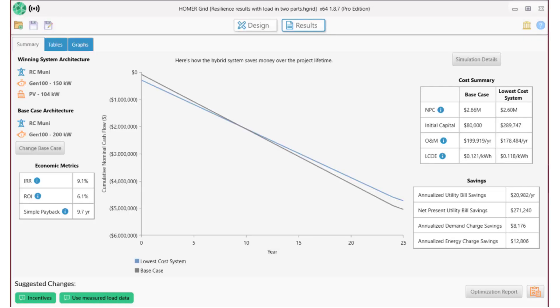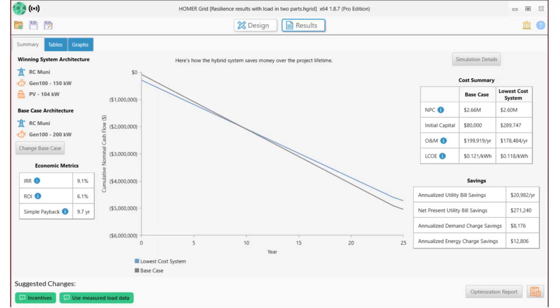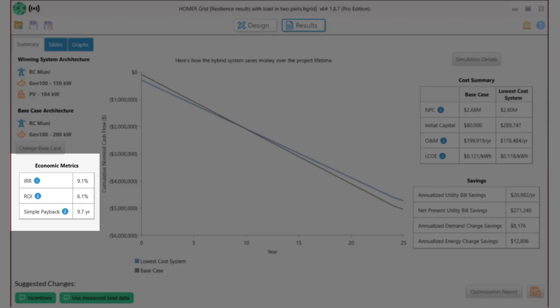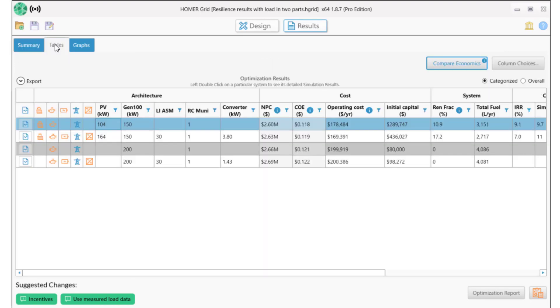The hybrid system saves money over the utility alone. The winning system in this scenario is the utility with a 150 kW generator and 100 kW of PV and storage. The base case includes the generator, so we're comparing the cost of the system with PV versus one without. The PV allows us to have a smaller genset by providing some of the power during outages. This system has an internal rate of return of 9%, an ROI of 6%, and a simple payback period of 9.7 years. It's saving about $21,000 per year in utility bills while also serving during outages.